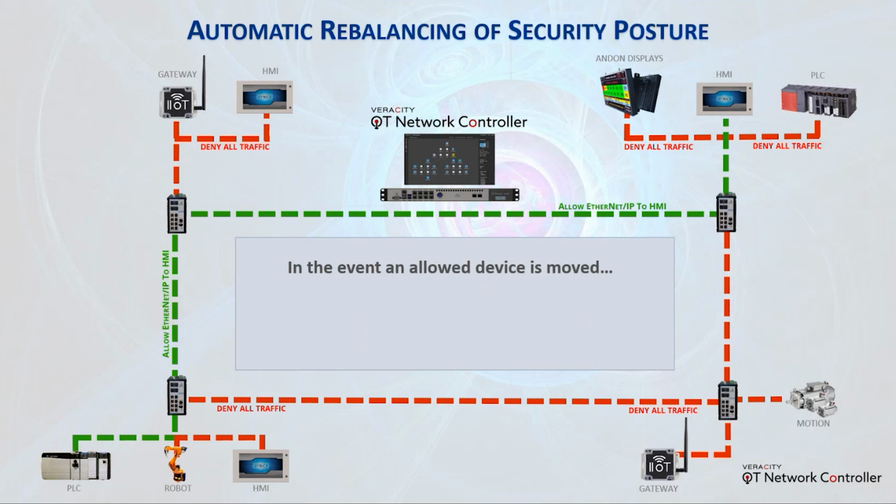Well, in the traditional network, that completely destroys your security posture because everything is moving. And as I mentioned earlier, being very port specific, it's a problem if you have to unplug PLCs from a port on switch A and move it to another port on switch B, because now all of the configuration that you built into that switch for that particular device and that particular port has to get moved, or probably won't get moved, and you'll have a hole in your security posture.